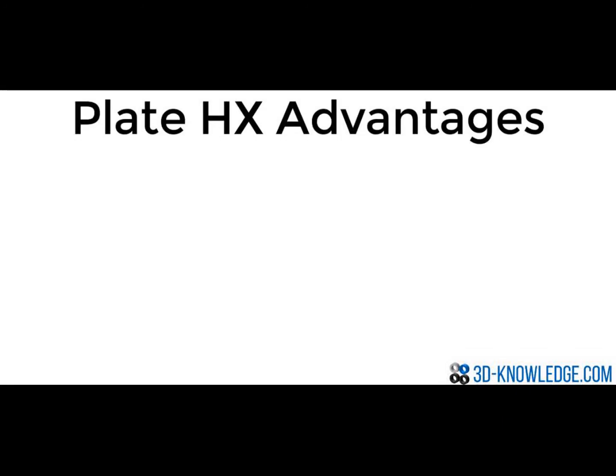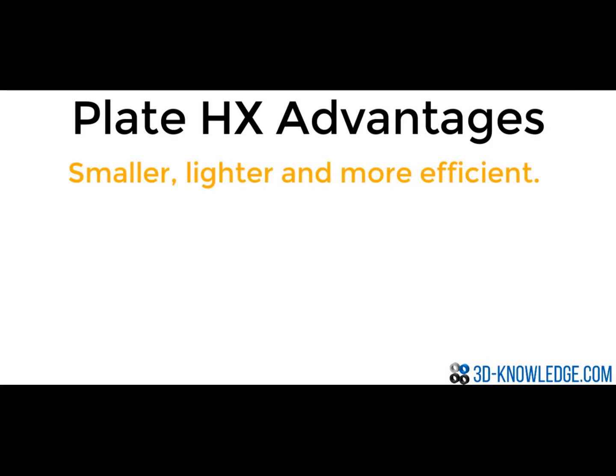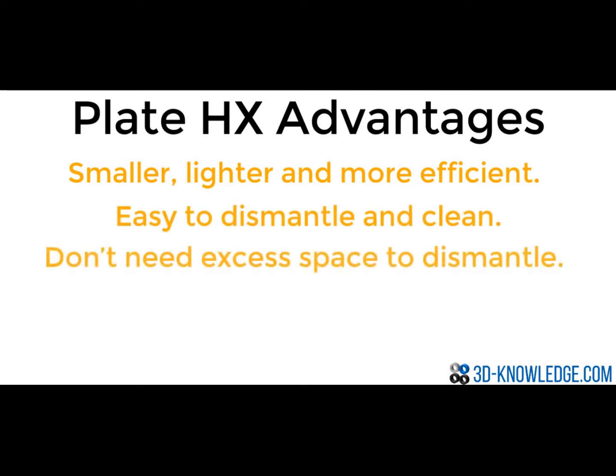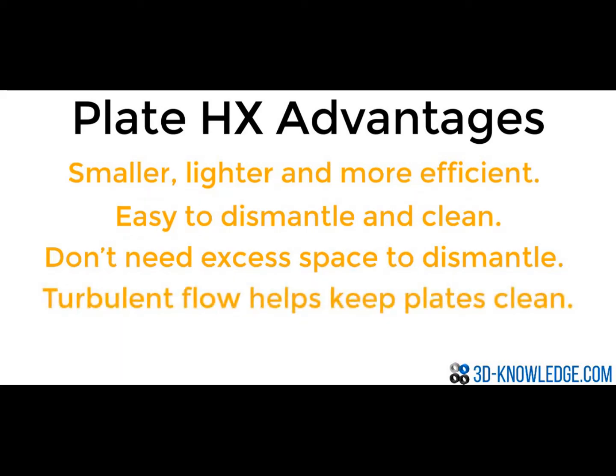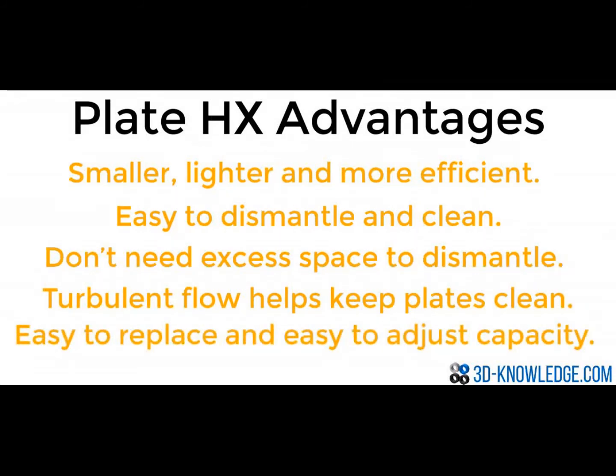The advantages with plate type heat exchangers are that they are smaller and lighter than tube heat exchangers. They're also more efficient when compared to tube heat exchangers of the same size. They're easy to dismantle and clean, and they don't need excess space to dismantle. Tube type heat exchangers do need a considerable amount of space in order that you can clean them properly. This is mainly because you need to pull the tubes out. Plate type heat exchangers don't have this problem. In addition to that, the turbulent flow in the plate type heat exchanger helps keep the plates clean, and it also helps break down the boundary layer of fluids that build up on the plate surface. The plates are relatively easy to replace, and you can actually increase or decrease the heat transfer capacity of the unit by adding or removing plates.